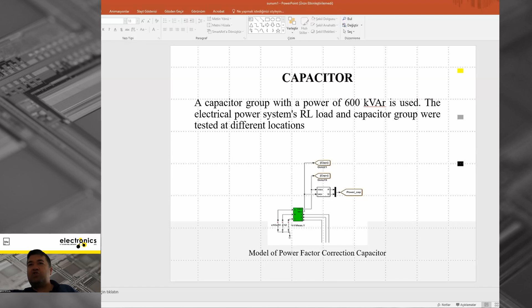And this is our electrical equivalent circuit. This side is the grid and grid impedance, and the grid line impedance, line 1 and line 2. And this is our capacitor bank. The other side is the PV inverter. The left side is the utility grid, the right side is the PV inverter side. And on the left, we used a breaker to make the reclose event on the line.